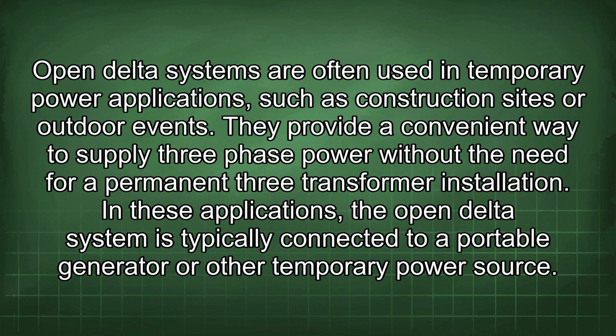Open delta systems are often used in temporary power applications such as construction sites or outdoor events. They provide a convenient way to supply three-phase power without the need for a permanent three-transformer installation. In these applications, the open delta system is typically connected to a portable generator or other temporary power source.